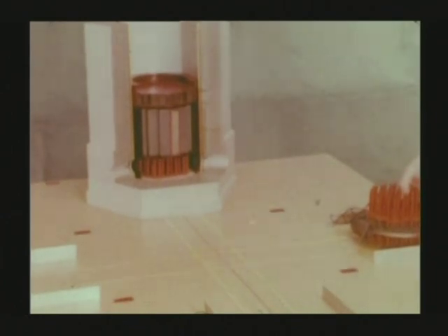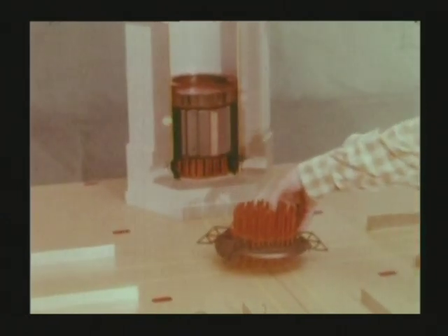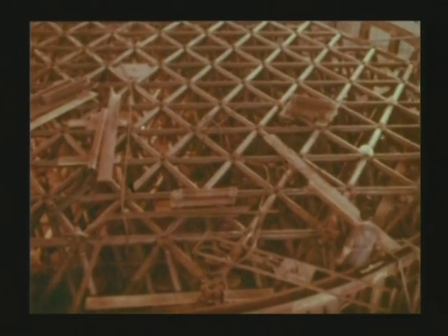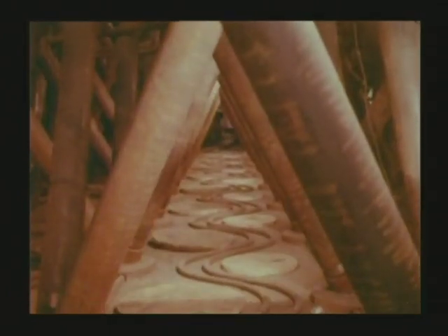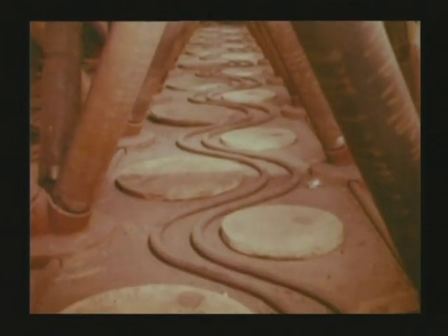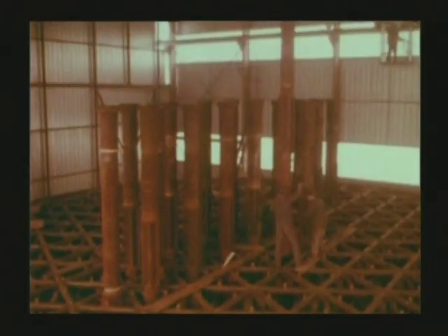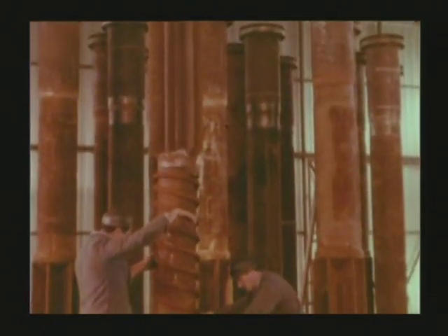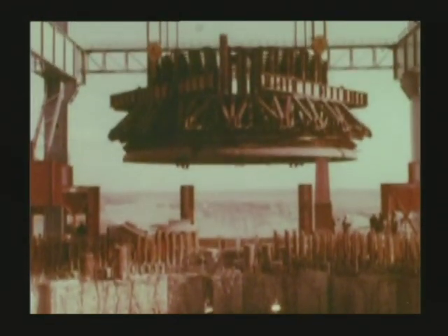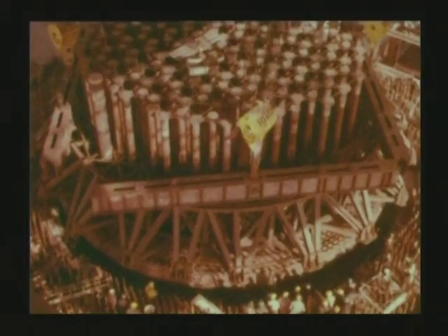The cover, or top slab, is the last bulky component to be placed in position. Its tubular framework is designed to withstand the stresses of concrete casting without distortion. Cooling coils cover the surface of the leak-proof plate, leaving free the shaft openings through which the fuel elements and control rods are to be inserted. Each shaft, welded to the cover, consists of a tube surrounded by cooling coils. This component, entirely assembled on the site, is finally raised to the top of the structure.